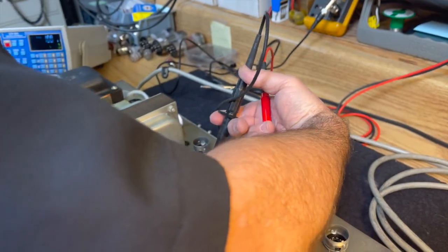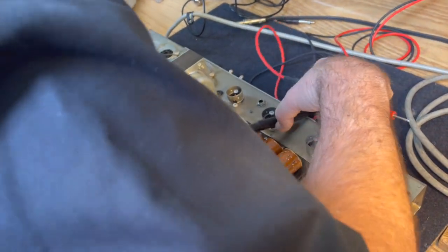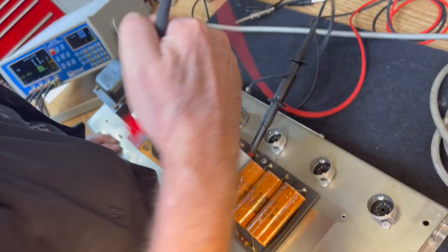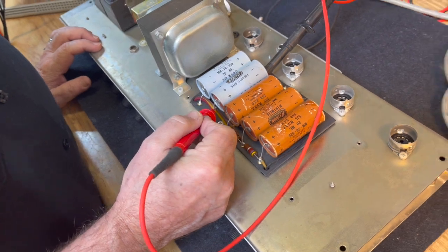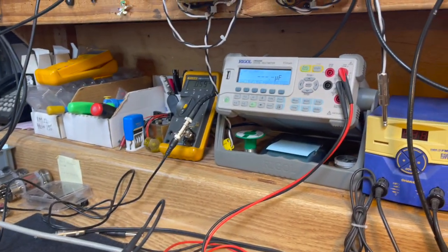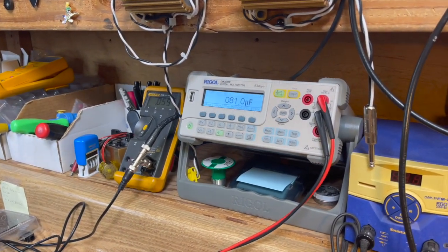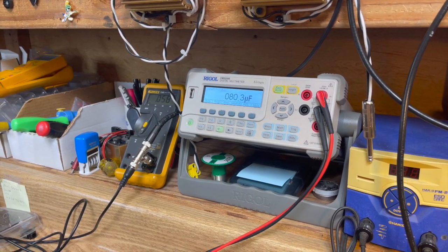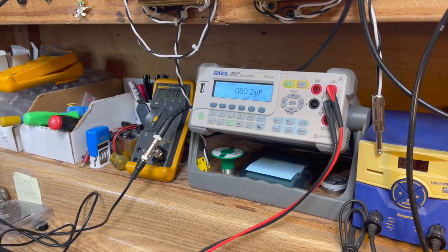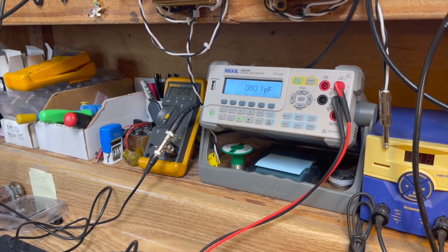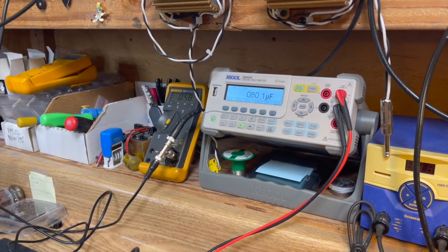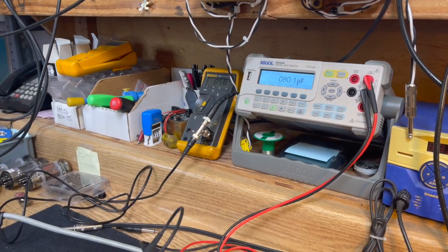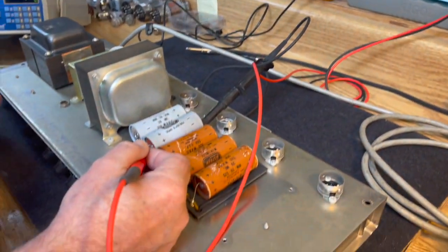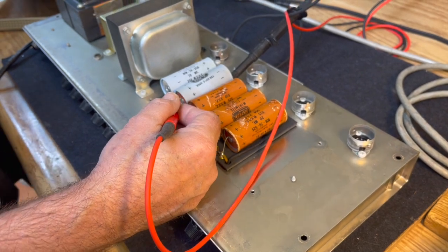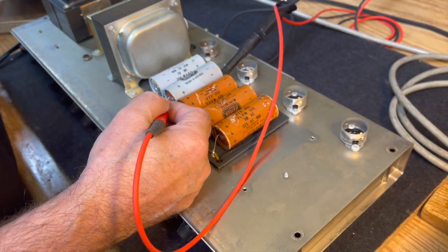Alright, so the next one, I'm reversing the polarity because it's installed with the reverse of the other one. And it is reading 79 mics, 80, 81, settling down to 80. Again, this meter is relying on sending a small residual voltage through the capacitor to arrive at that reading, and it hasn't had any voltage applied to it for 20 years. So once we bring the capacitors up to their normal operating voltage and then go test these all again, we're going to get different readings.